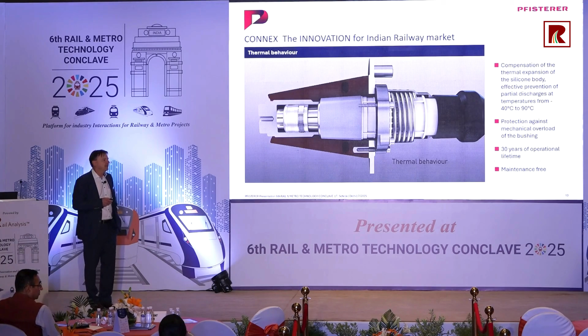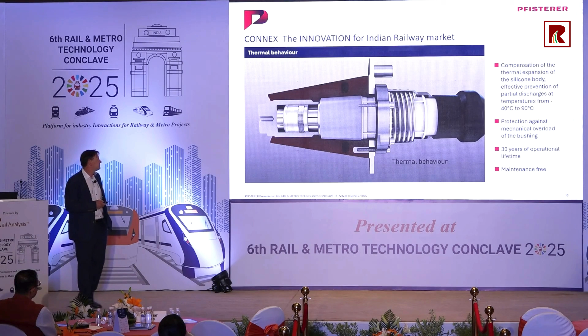So what's important about this, and why is this feature critical? Because if you want a medium voltage system operating for 30 years, you need to avoid any partial discharge and any risk of electrical failure. This thermal compensation reduces the possibility of partial discharge in the connections to a minimum, and that's why this system is well protected and can operate for 30 years.